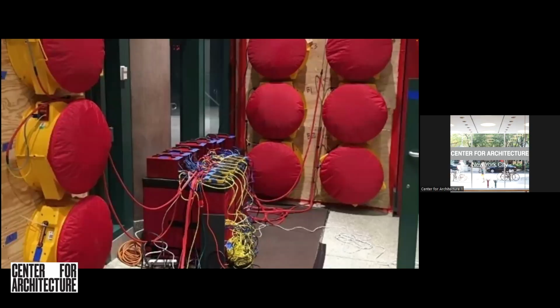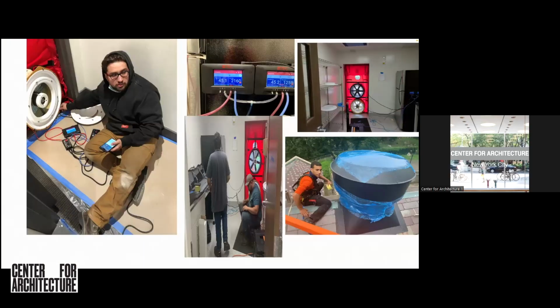Because it's not comfortable to have unconditioned air constantly exchanged through the envelope of that building. This slide's a little off, but this is a difficult test to perform, as you can see from this picture. People in New York aren't used to doing the test. They don't understand the process or how performing it has to be scheduled into construction.